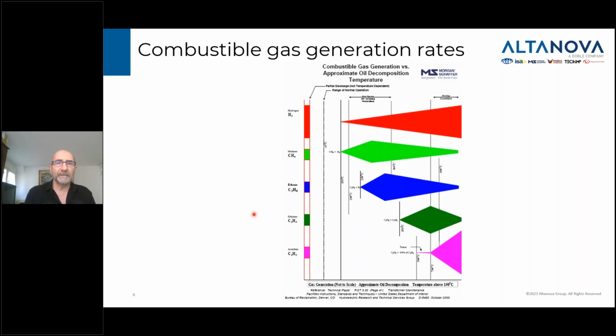Another way to look at it is this chart. This chart tells you the rate of generation of the gas depending on the temperature. What this shows is that when you get to a temperature of around 140 degrees, the rate of generation of hydrogen increases. And as a fault develops, the temperature will increase from 140 up, as I said earlier, to potentially 1200 degrees C. The hydrogen rate of generation always increases.